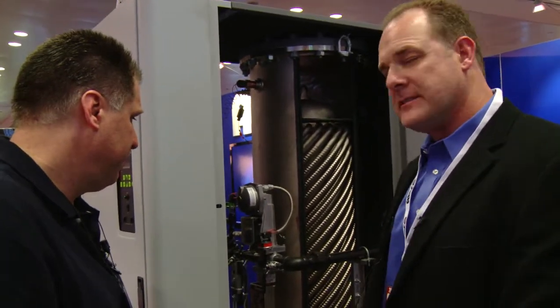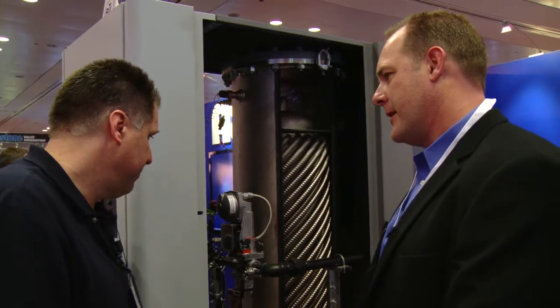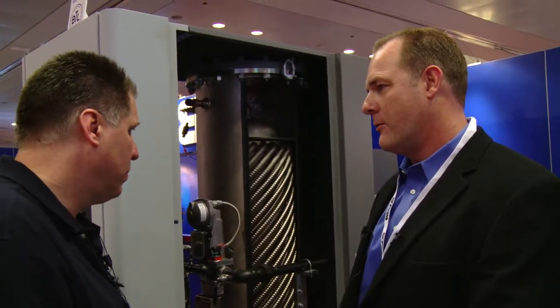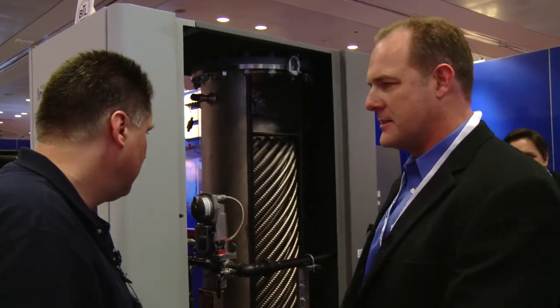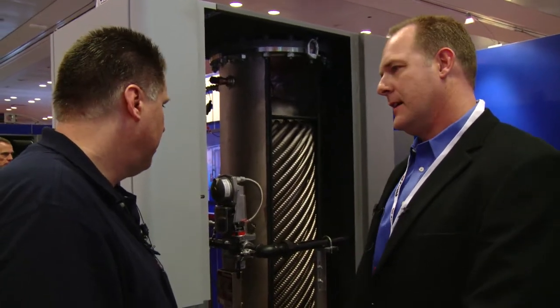The efficiency of this product is up in the 95% range, to where the exhaust temperatures are generally only about 10 degrees higher than the water temperatures. Since that exhaust temperature is so low, this is listed to vent with PVC vent, both direct out of a sidewall or up through a roof of a building.